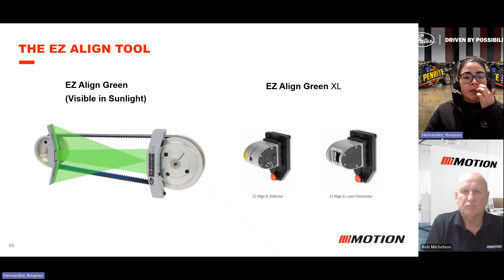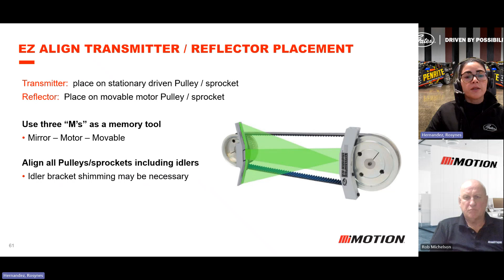You have a transmitter, normally installed on the driven pulley, and a reflector, which has the mirror. The reflector always has to be on the motor, which is the one you adjust to get the alignment, and the transmitter has to be on the driven. A quick way to remember: mirror on the motor, and you can move the motor. So the mirror has to be on your motor side.